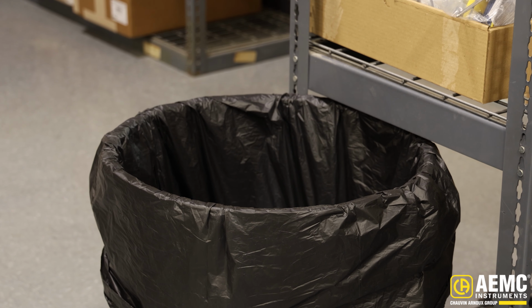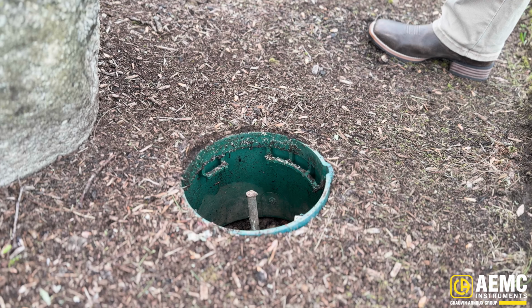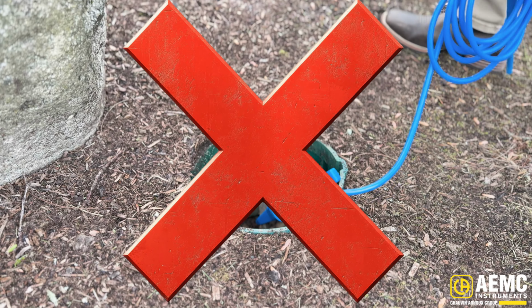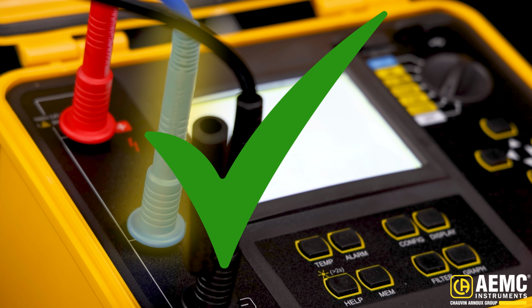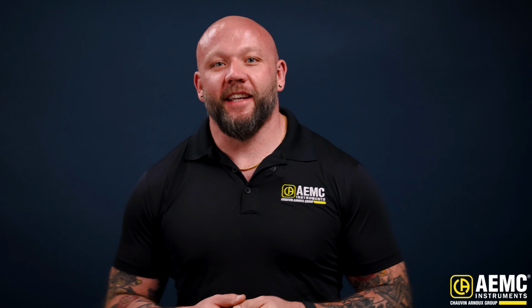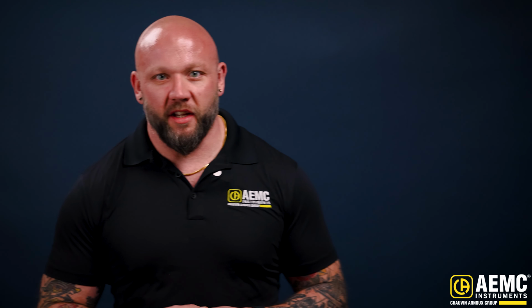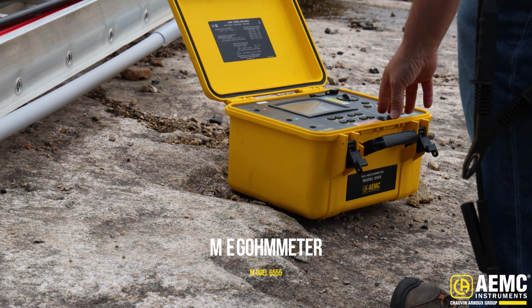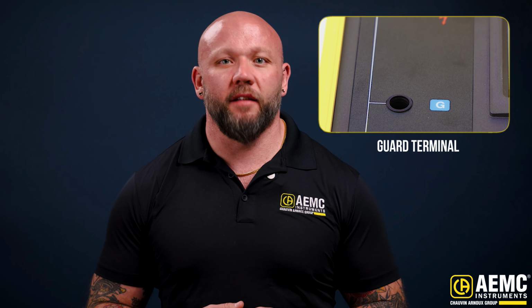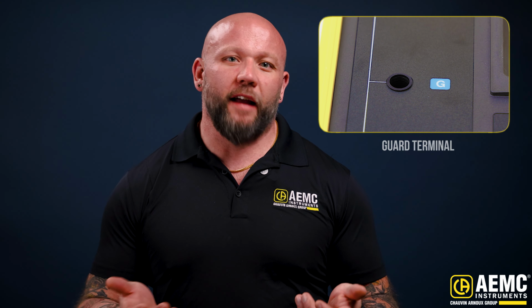It's not the garbage lead, and it's not the ground lead. It's a guard lead. Hey, I'm Gregg with AEMC Instruments. If you're performing insulation resistance testing with a precision instrument like the AEMC Model 6555, you've probably seen the guard terminal. But what's it exactly for?